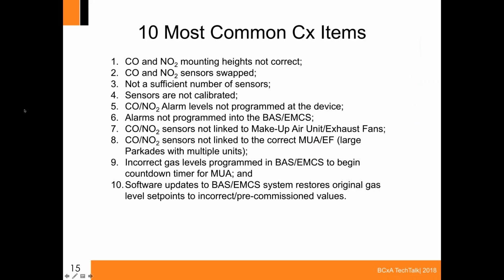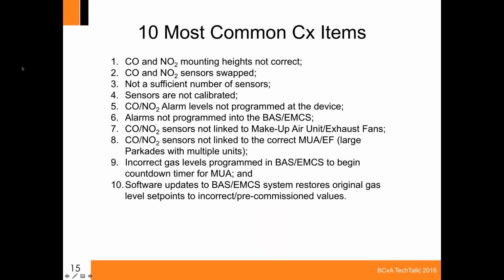So moving on to the final portion of this, the 10 most common commissioning items that I've run into are: the mounting heights are not correct. The sensors are swapped. Someone has gone and moved the CO sensor and the NO2 sensor and swapped them. There haven't been a sufficient number of sensors. That's where I said to check with your city inspector or the authority having jurisdiction and make sure that you know how many need to be there for when you're doing your commissioning. The sensors arrived in the field not calibrated correctly from the factory, so they have to be set up.